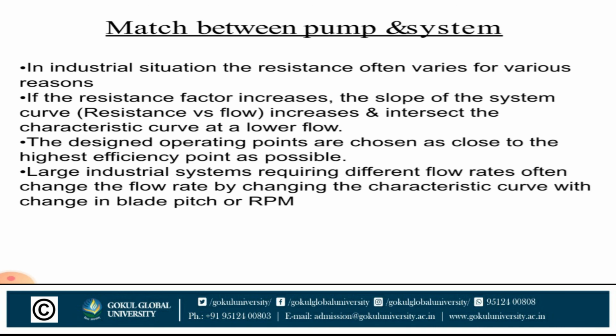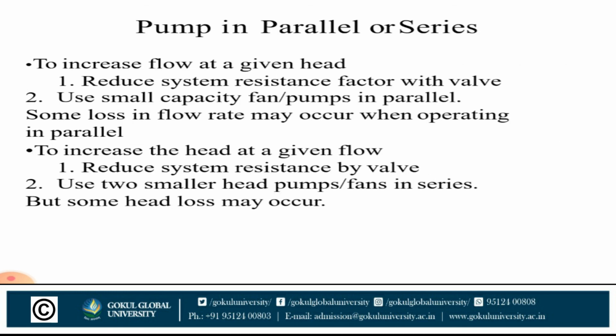In industrial situations, the resistance often varies for various reasons. If the resistance factor increases, the slope of the system curve increases and intersects the characteristic curve at a lower flow. The design operating point is chosen as close to the highest efficiency point as possible. Large industrial systems require different flow rates, often changing the flow rate by changing the characteristic curve with a change in blade width, blade pitch or RPM.